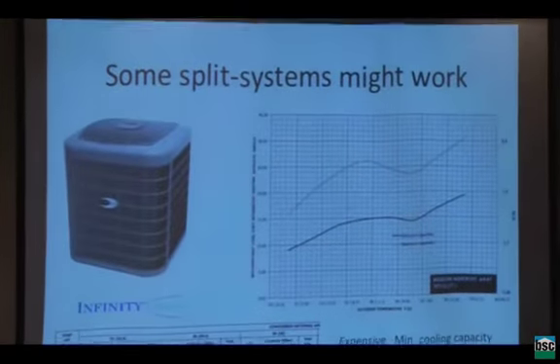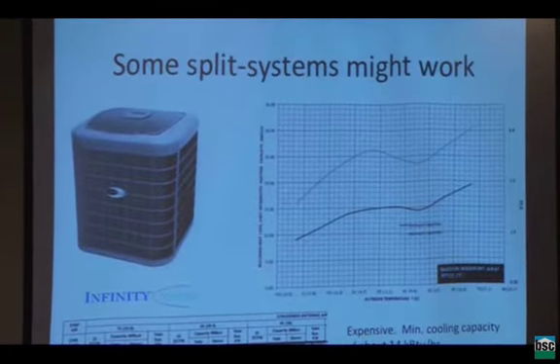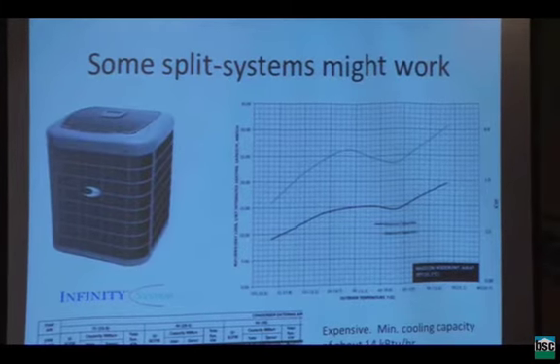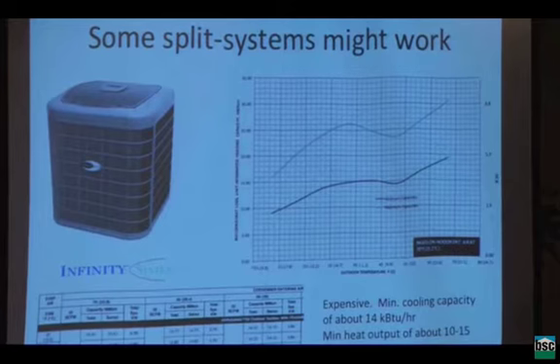Well, here's an Infinity, what they call it, Greenspeed Plus, with the Infinity Plus system from Carrier. It's a variable output. It gives me between 10 and 15,000 BTUs an hour at outdoor temperatures of 0 degrees Fahrenheit. And yet, at a temperature of 50, it only gives me 15,000. So that's actually tolerable, and that is not a huge range. And I can run it when it's 50 degrees outside. I only have to run it 10 or 20 minutes an hour. And when it is 0 degrees outdoors, I run it 60 minutes an hour. So these things start to get to reasonable performance.